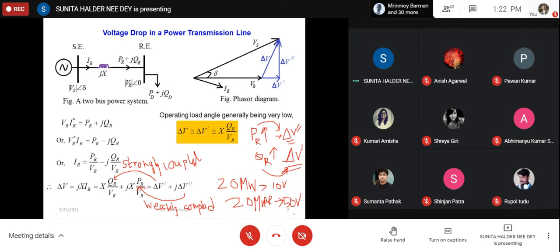Yes, ma'am. Similarly, just opposite, if we want to transfer 20 megawatt power, then change in delta will be more. If for 20 megawatt power, the change in delta is 30 degrees, if you keep both end voltage fixed, then you are just by changing delta, you want to change the power.